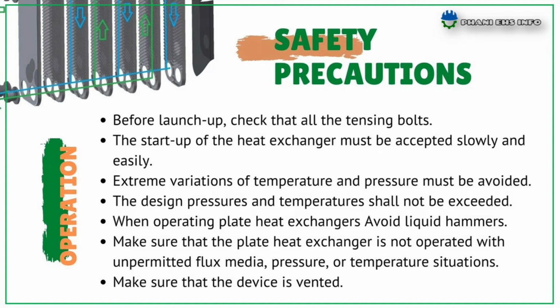The design pressures and temperatures shall not be exceeded for each model, which are marked on the nameplate. When operating plate heat exchangers, avoid liquid hammers. Make sure that the plate heat exchanger is not operated with unpermitted flux media, pressure, or temperature situations. Make sure that the device is vented.